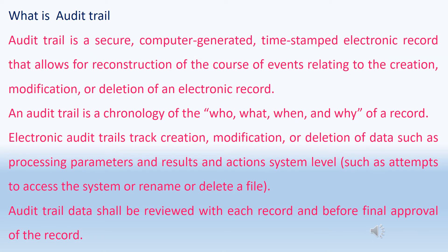What is an audit trail? An audit trail is a secure, computer-generated, time-stamped electronic record that allows for reconstruction of the course of events relating to the creation, modification, or deletion of an electronic record. An audit trail is a chronology of who, what, when, and why of a record. Electronic audit trails track creation, modification, or deletion of data such as processing parameter changes, results, and actions at the system level.